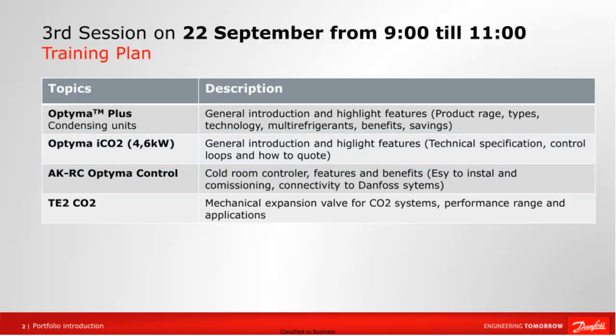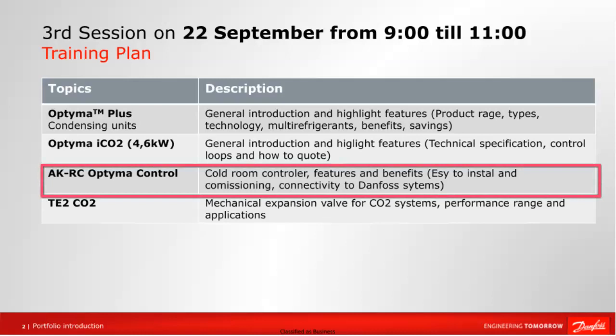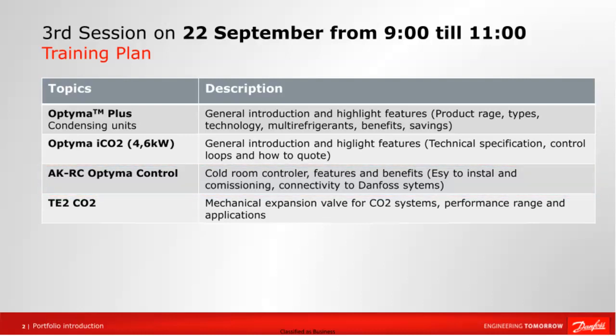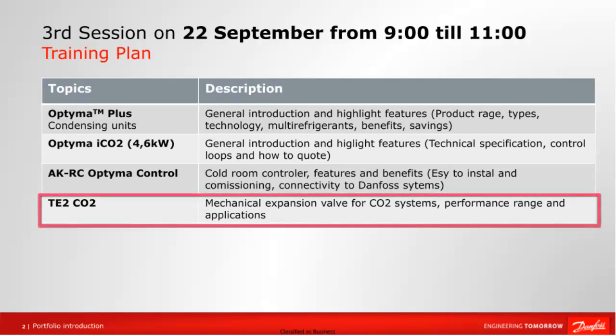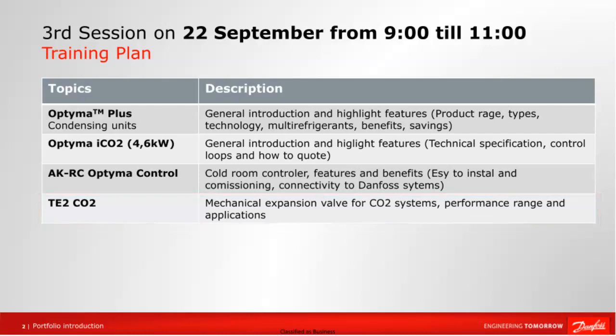The next issue is the AK-RC Optyma Control Cold Room controller. Here I would like to present the basic advantages of this controller. For example, easy installation and parameterization, and emphasize its communication capabilities with other Danfoss systems. And finally, I would like to present a thermostatic expansion valve for CO2 installation, what performance range can be handled, and what applications can be used for.